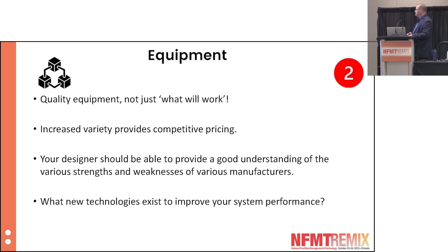The third piece is installation. Does your fire alarm vendor have the installation skills for a large fire alarm replacement? They might be a great vendor, a great programmer, and know exactly what their manufacturer's equipment does, but they may be really bad at installing the system—and they may have to subcontract.